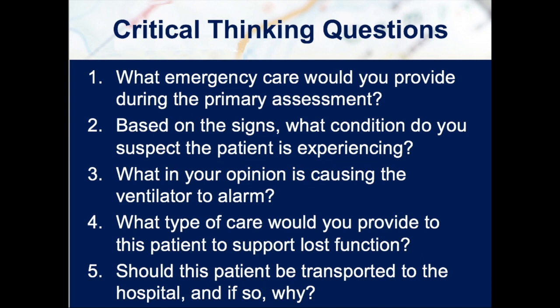The second question is, based on the signs, what condition do you suspect the patient is experiencing? Kind of gave that one away, but we have a high pressure alarm and you're hearing a lot of gunk in the tracheostomy tube. So you should be thinking this patient probably has an occlusion. The machine is saying, I'm having to push a lot of pressure into the tracheostomy tube to get the amount of air in that the machine wants to get in. So that's a high pressure alarm. And then you're hearing those noises, so that's a good clue that there's an occlusion.